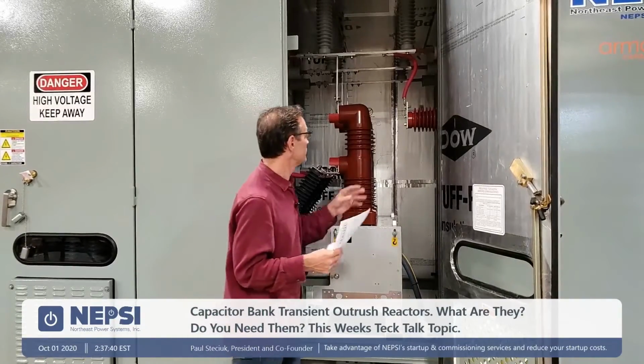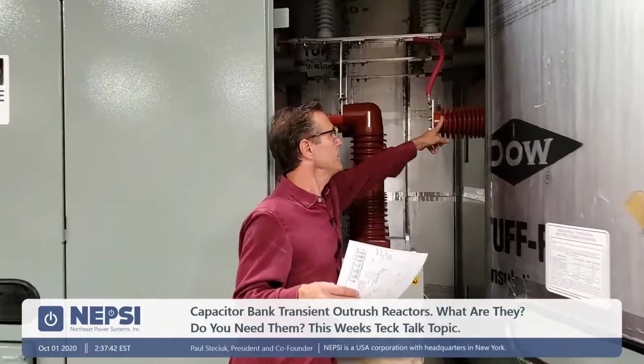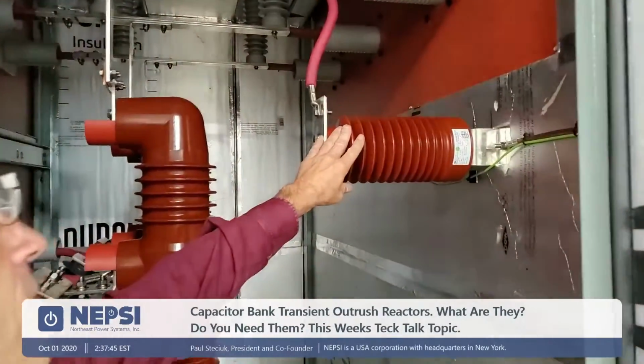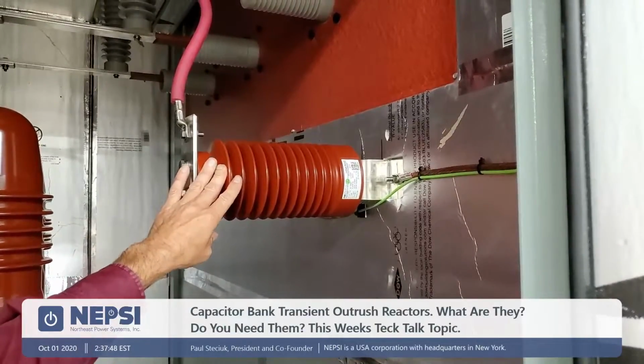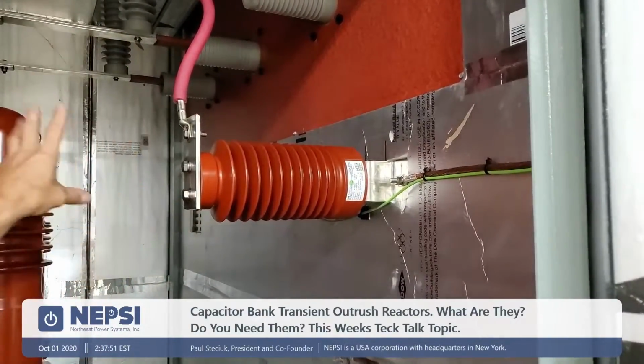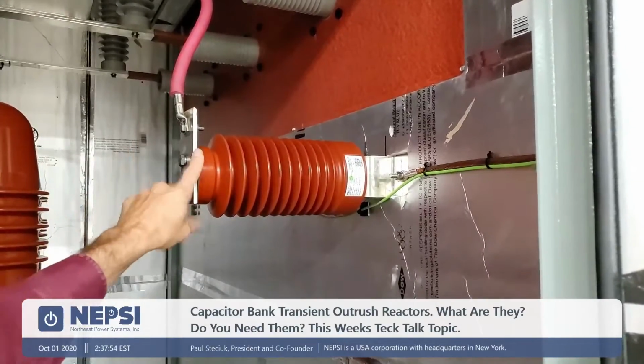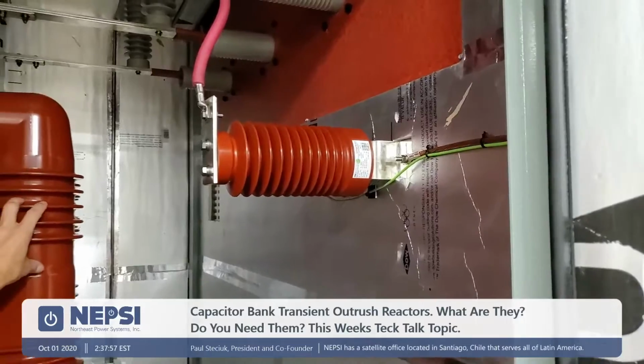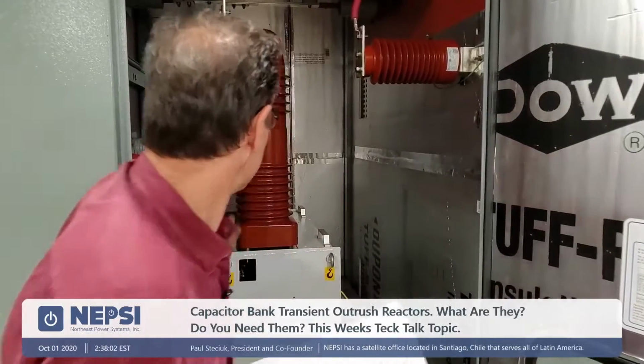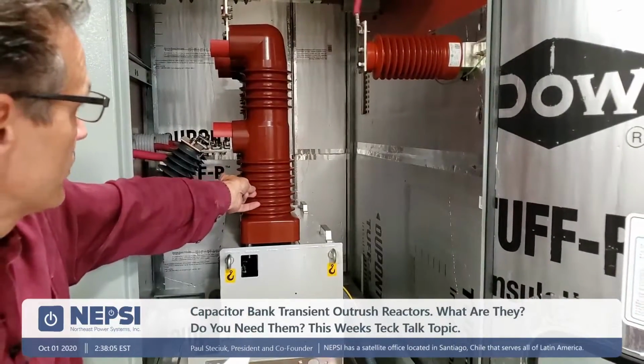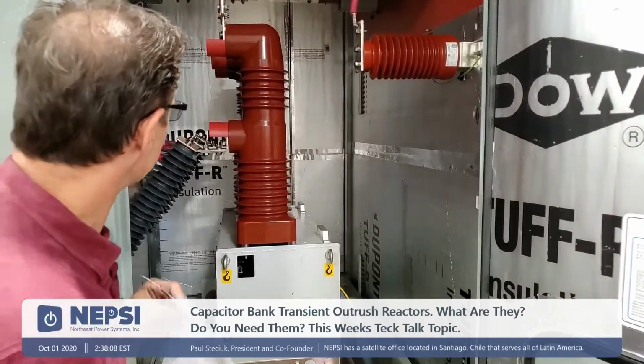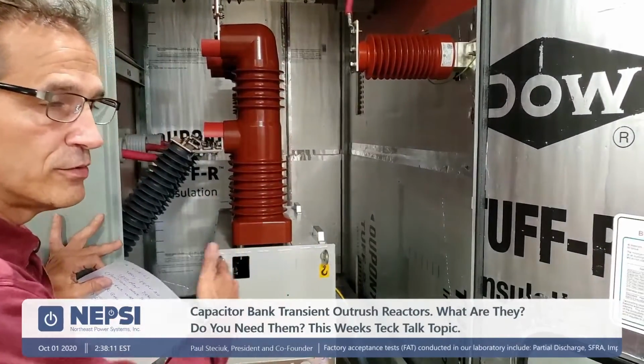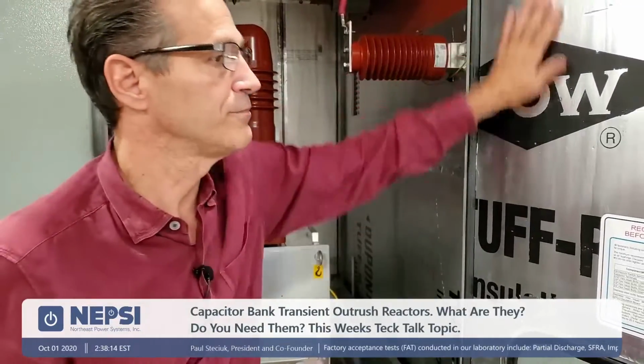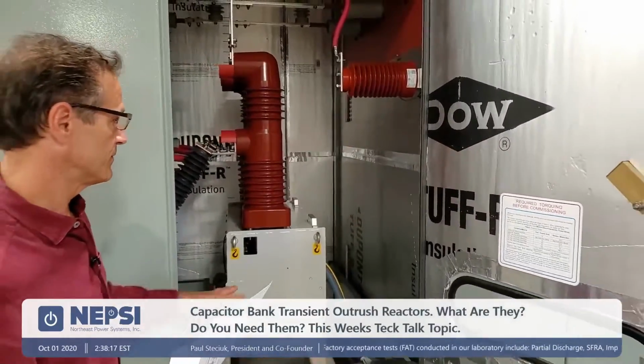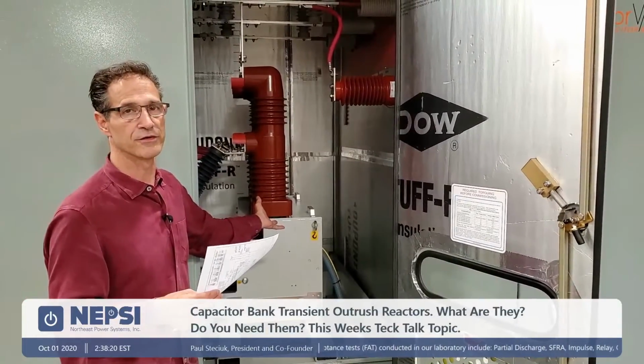So if you just poke your head in here maybe a little bit, you can see this is the voltage sensor. So we're connected to phase A line side, and we're sensing the phase A voltage, and we're closing on zero voltage, okay, with this device. And the electronics and the knowledge of when to close is inside this switching device. You can see that we have some line side lightning arresters. That's a specification requirement for this project. And it's in an isolated cubicle. It's in its own compartment, and we've insulated the compartment. And we do that because this has a temperature rating, a minus 20 degree Celsius temperature rating.